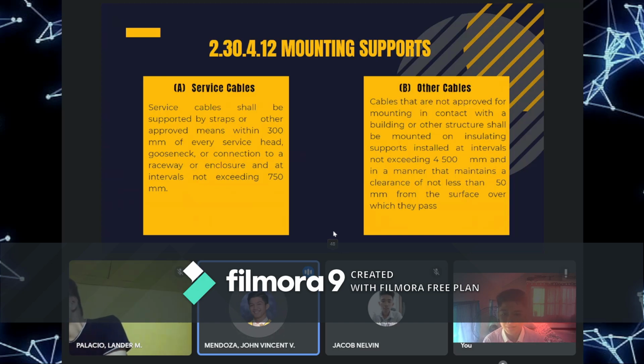So para sa ating mga service cable, dapat supported siya ng mga clamps or insulators. And dapat may support yung cable every 300 millimeter every service head or raceway. And dapat kada interval ng support ay dapat hindi lalagpas ng 750 millimeter para maiwasan ang pagkasira ng ating cables. And hindi din siya sasayaw kung may wind current na padating.